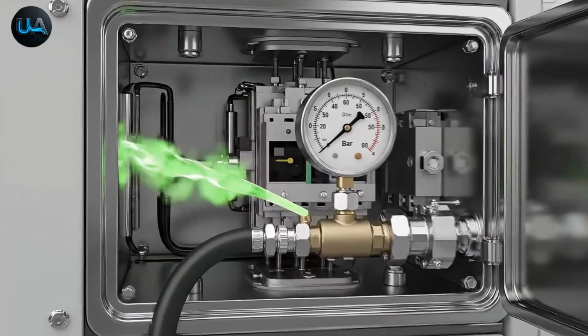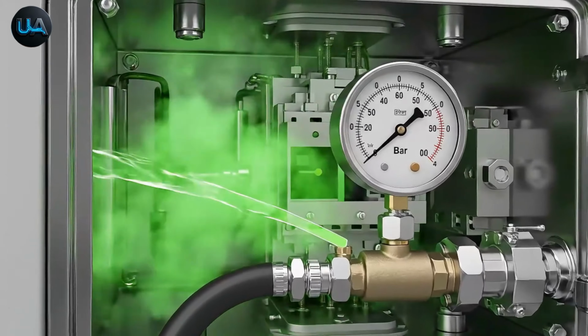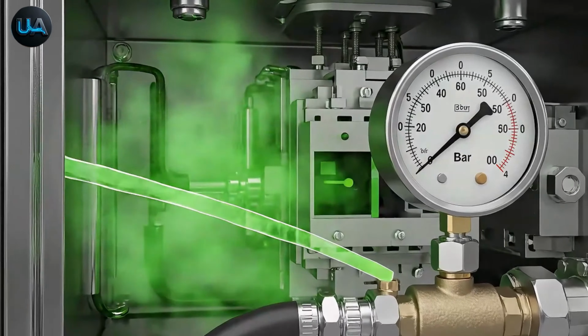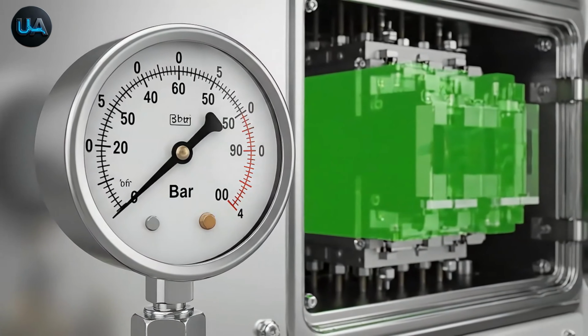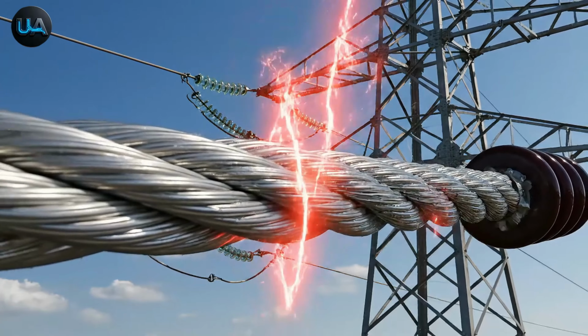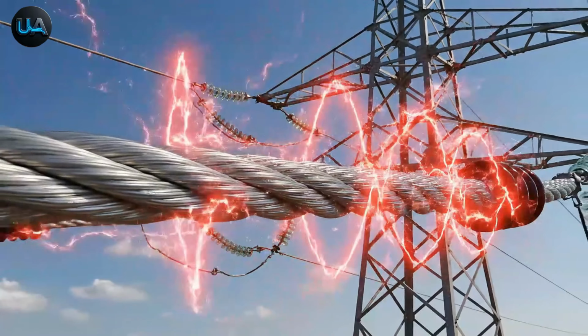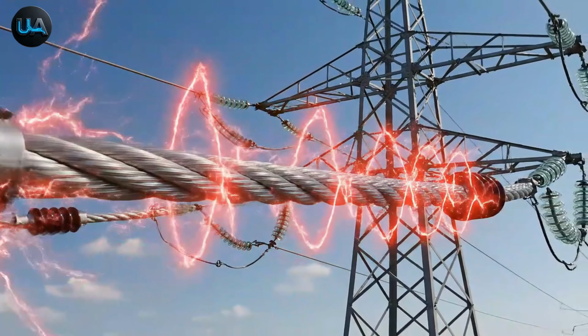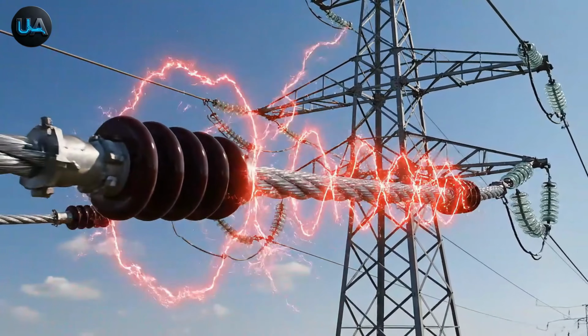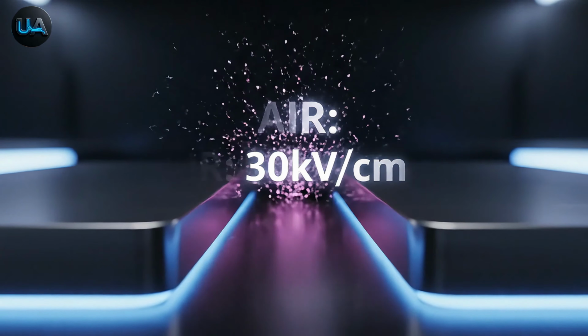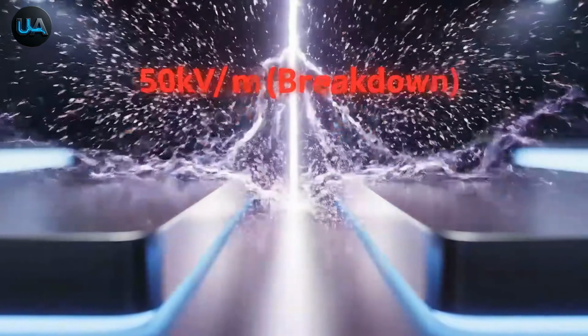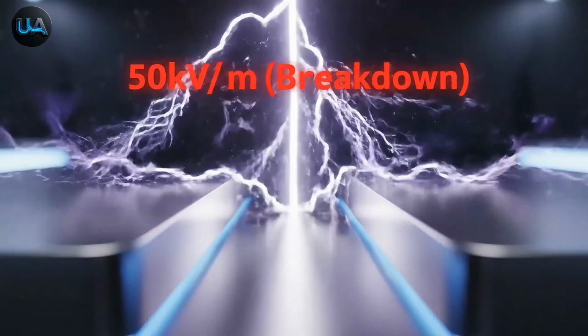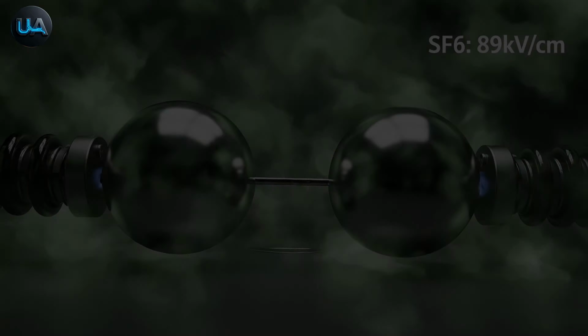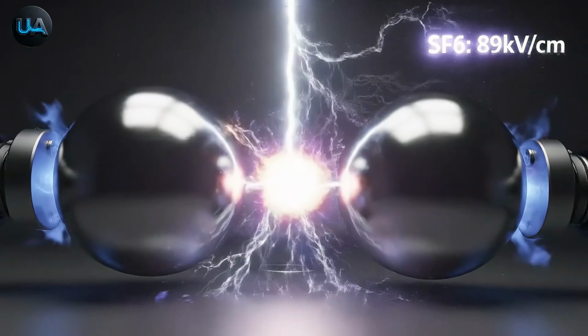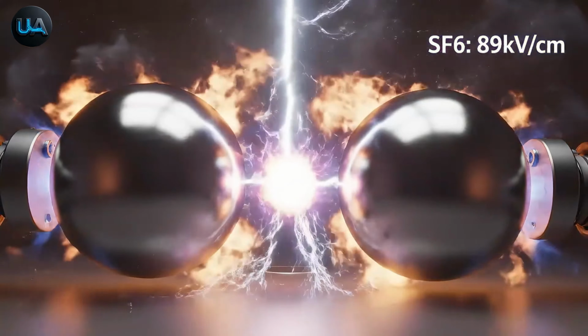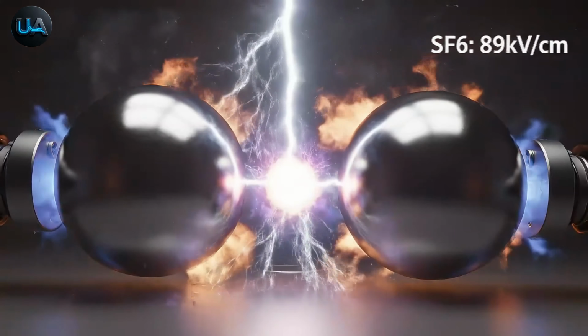Compartment. Each of these compartments is filled with sulfur hexafluoride, or SF6 gas, which is a much better insulator than air. In a normal high-voltage line, an electric field is generated in the air around the conductor. But SF6 gas has a dielectric strength of about 89 kilovolts per centimeter, which is almost 3 times higher than air.